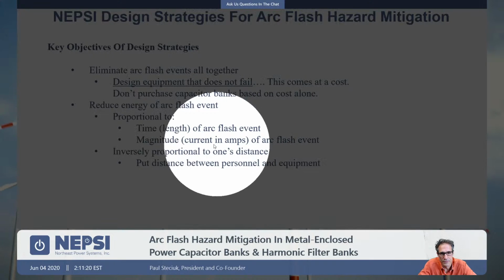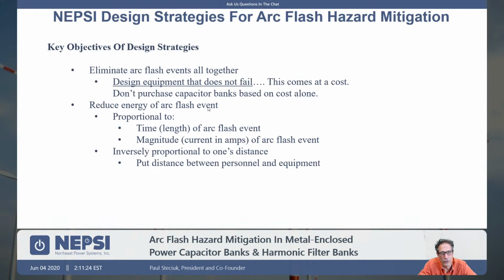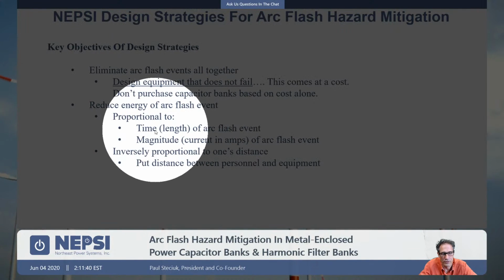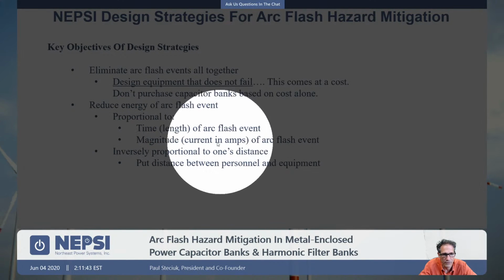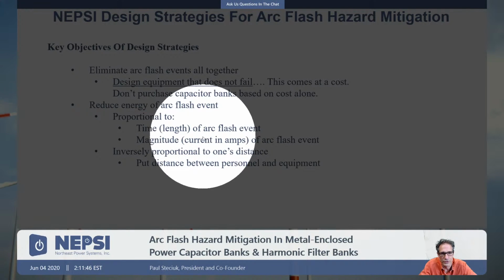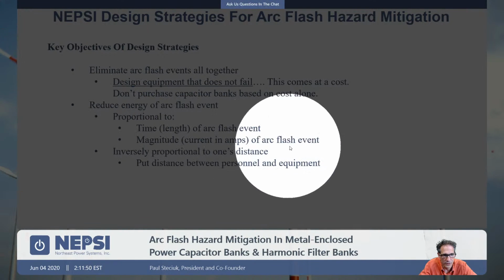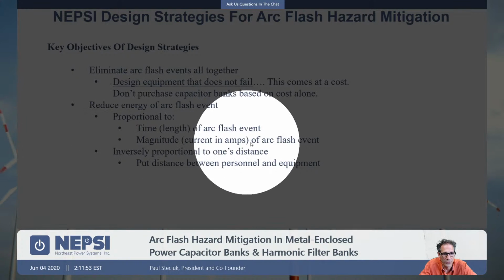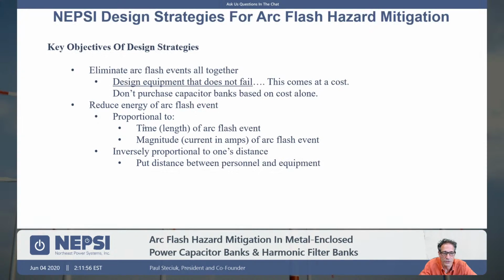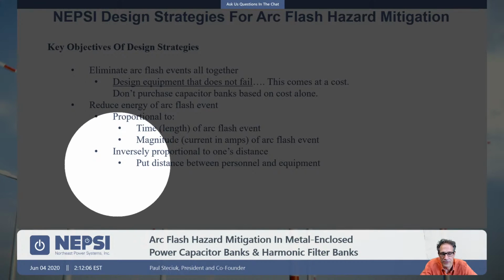You also want to reduce the energy of an arc flash event. Remember, when an arc flash event occurs, you have arc through air, and it's fault current that is flowing. Fault current times time is related to how much energy is going into that arc flash event. So if we can reduce the time of the fault, or if we can reduce the magnitude of the fault current, we can reduce the energy into the fault. So we oftentimes look for ways to reduce these items, and this is in the protection system that we can do that. We can supply current limiting fuses, which provide our current limiting mode and also interrupt fault currents very quickly, on the order of 4 milliseconds, so very quick. And then also think about the site conditions.